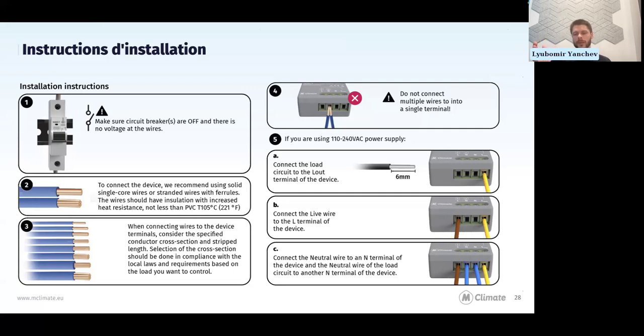If you use stranded wires, we advise using ferrules on top. Since it's 16 amps, choose the cable size depending on the load—if you use a super thin cable for 16 amps, it's just going to burn. Also, don't install two cables into one terminal; that's why we have two ends here, because we don't want people putting two cables into one terminal.